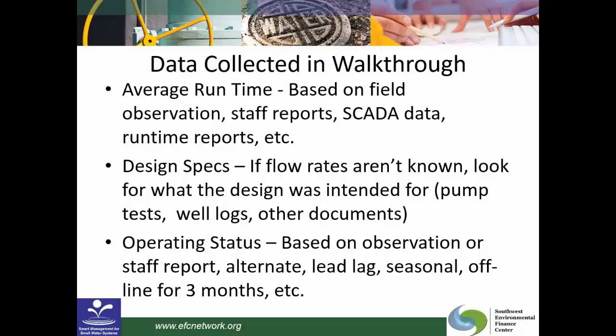Design specs: if we don't know what the pump is currently pumping, what the flow rate is, look for what the design was intended for. And it could come from pump tests, from well logs, from the documentation that came with the O&M manual, places like that that you can look.